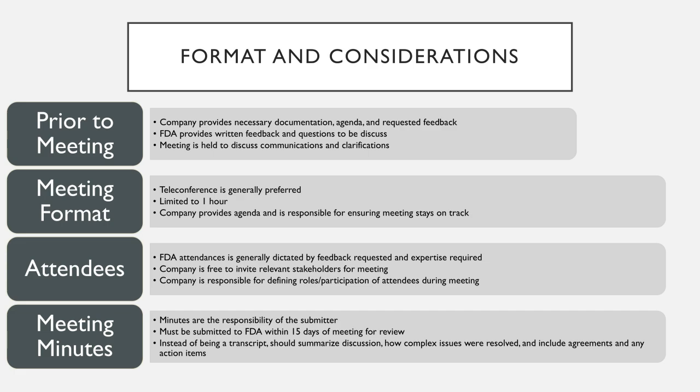Now, the company is also responsible for maintaining the meeting minutes, which are going to represent the formal log of whatever decisions came about throughout that meeting. In fact, it's something that they have to submit within 15 days to the FDA as part of the official Q-sub log process. And the FDA then is going to have a chance to agree to those meeting minutes or maybe ask for amendments with that company, because it does represent some type of non-binding agreements between the two. Those meeting minutes themselves shouldn't be a transcript, but simply a summary of the discussions, particularly on any relevant decisions or feedback that was given on any particular issue.